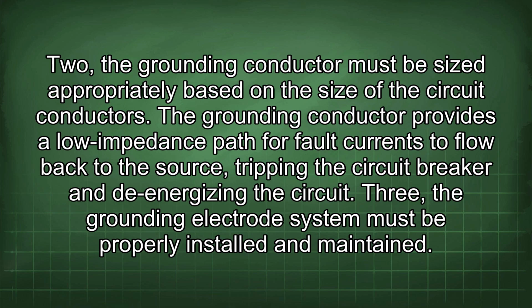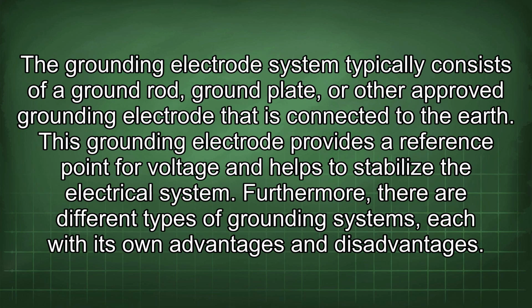2. The grounding conductor must be sized appropriately based on the size of the circuit conductors. The grounding conductor provides a low impedance path for fault currents to flow back to the source, tripping the circuit breaker and de-energizing the circuit. 3. The grounding electrode system must be properly installed and maintained. The grounding electrode system typically consists of a ground rod, ground plate, or other approved grounding electrode that is connected to the earth. This grounding electrode provides a reference point for voltage and helps to stabilize the electrical system.